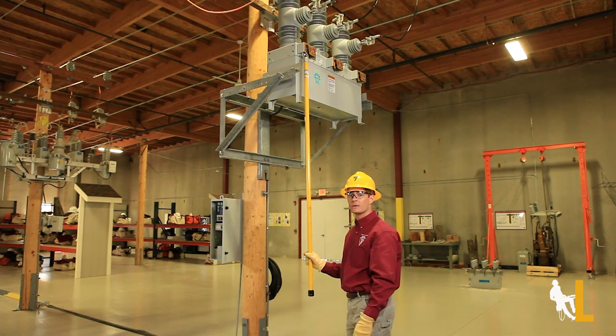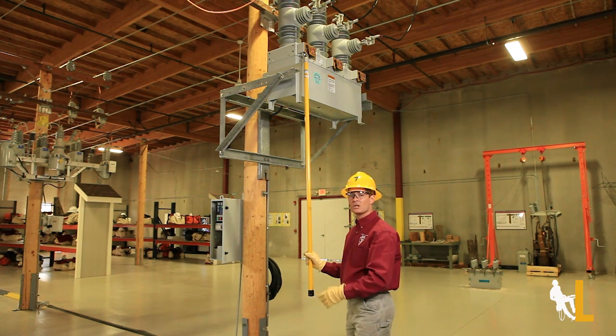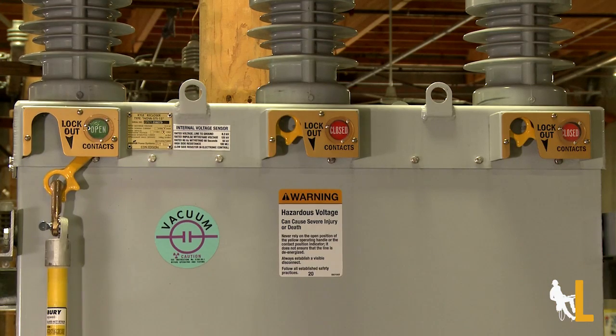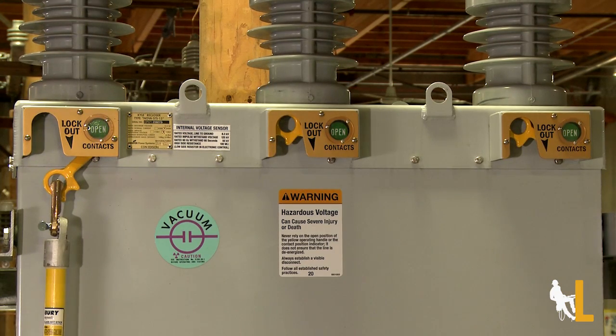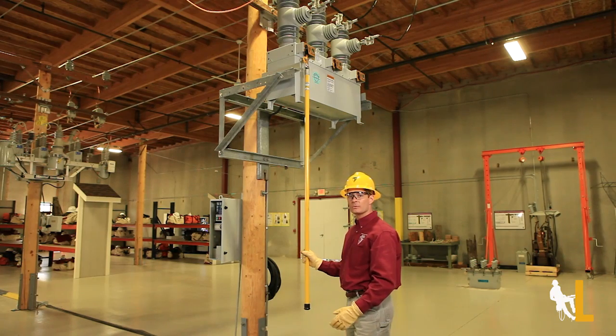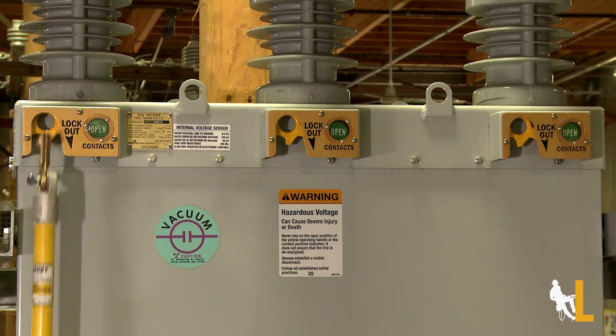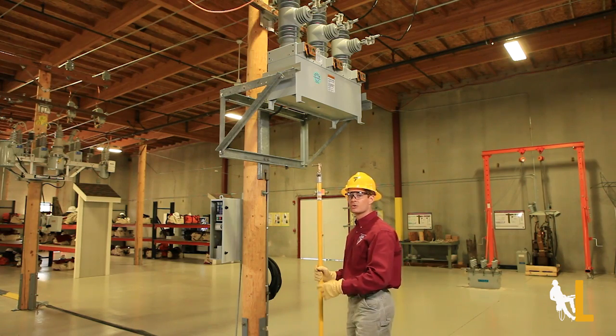Since this recloser is set on a three phase lockout, pulling down on just one yellow handle will open all three phases. If it was set on a single phase lockout, then the yellow handle you pull down would open that phase. To close the recloser, go ahead and push the yellow handle back up. But this does not actually close the recloser. It can only be done from the control panel.